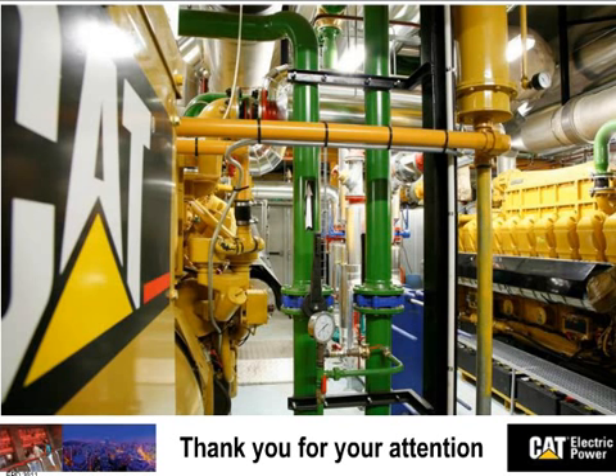That's the beauty of our lean burn low pressure gensets. We also have in our range high pressure gensets when available. We have both technologies. But lean burn is nice with low pressure because you can actually install this cogen, this CHP power plant, downstream and remote from the gas grid. Imagine you're far away from a gas distribution pipe, so your gas utility will deliver gas only at quite low pressure. That would require, for a turbine, for instance, a compressor. For us, we don't need any compressor. We can live with 200 millibars and 100 millibars at the engine.